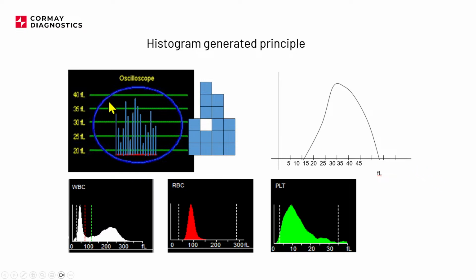If we take an oscilloscope and try to see the sizes of the particles passing through the aperture, we will see something like this, right? It will be information about the size of the particle over time. Let's say we have femtoliters on this scale, and time. What the analyzer is doing is counting the number of particles of each size and simply adding those to the histograms.